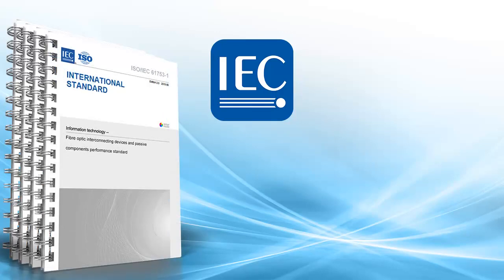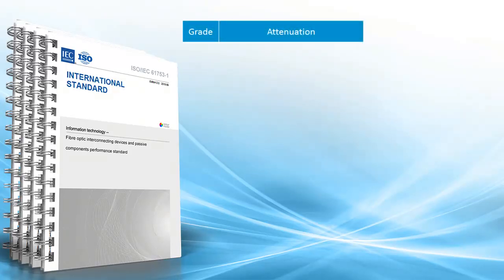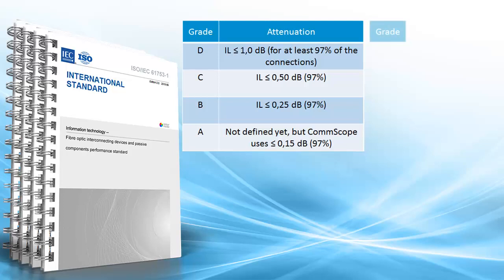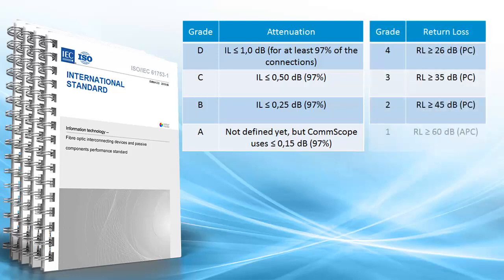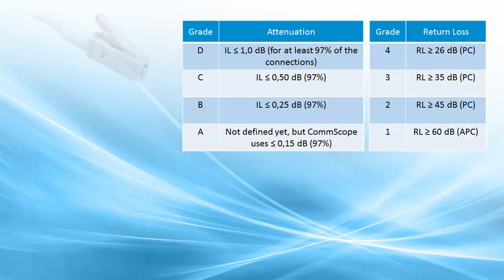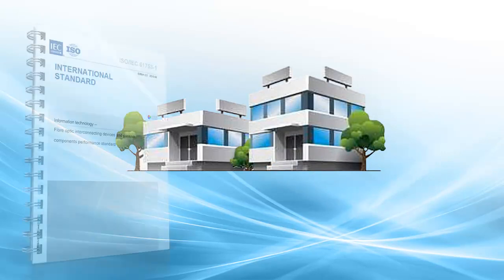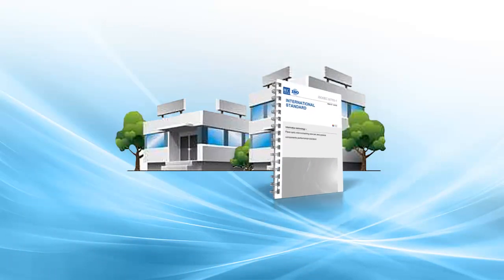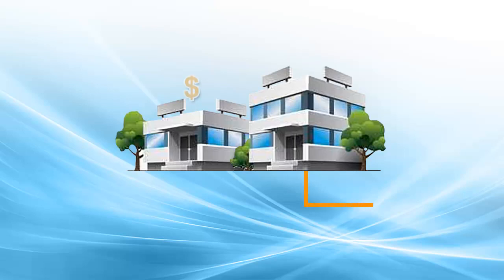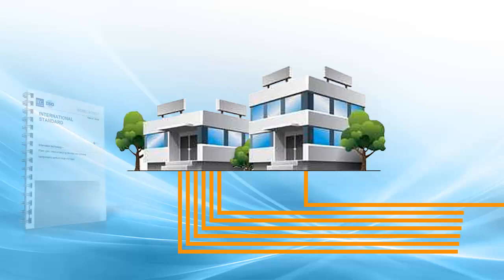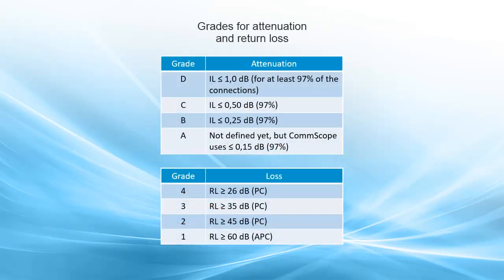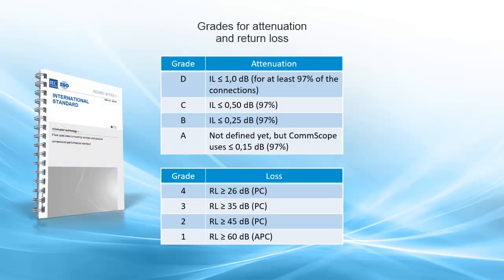The standard IEC 61753 describes application-oriented grades for connection elements in fiber-optic networks. It provides clear grade identification and necessary IEC test method to aid planners, as well as those responsible for networks, to make the correct selection of plug-in connectors, patch cables, and pigtails. Data center operators and telecommunications companies can determine their fiber-optic specifications according to usage and make faster and more informed purchasing decisions. This also avoids purchasing of over-specified products, which do not deliver the expected loss values claimed. The current requirements list shown here is based in part on IEC 61753 and defines the loss values according to the grade.